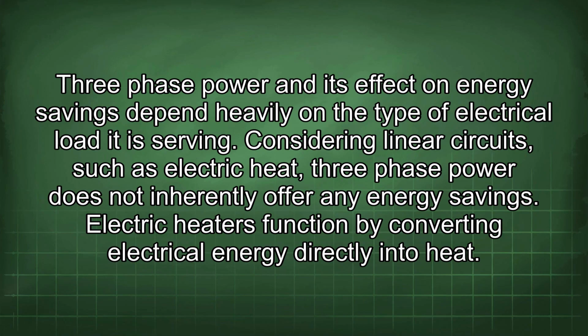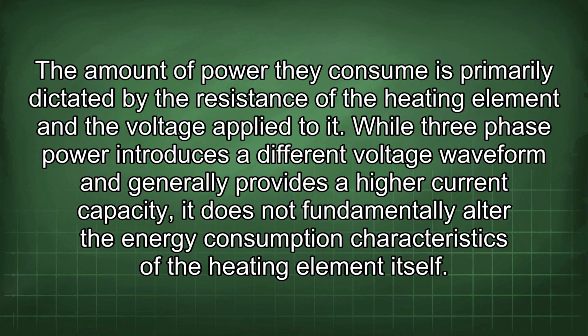Three-phase power and its effect on energy savings depend heavily on the type of electrical load it is serving. Considering linear circuits, such as electric heat, three-phase power does not inherently offer any energy savings. Electric heat functions by converting electrical energy directly into heat. The amount of power it consumes is primarily dictated by the resistance of the heating element and the voltage applied to it. While three-phase power introduces a different voltage waveform and generally provides a high current capacity, it does not fundamentally alter the energy consumption characteristics of the heating element itself.